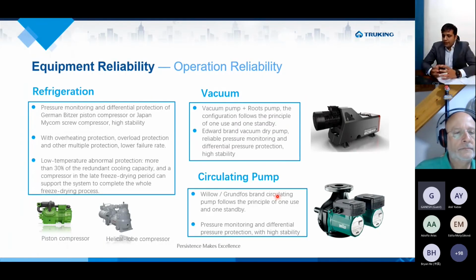So again, from the equipment reliability point of view, we have already discussed the workmanship that is required to make these kinds of machines. Then further, in the refrigeration and in the vacuum skid, we also need high quality pumps and compressors. In the refrigeration, the pressure monitoring and differential protection is achieved by either the reciprocating compressor from Bitzer, which the user can choose, or a dual stage screw compressor from Micom. They also have overheating protection, overload protection, and multiple other protections in case of failure.